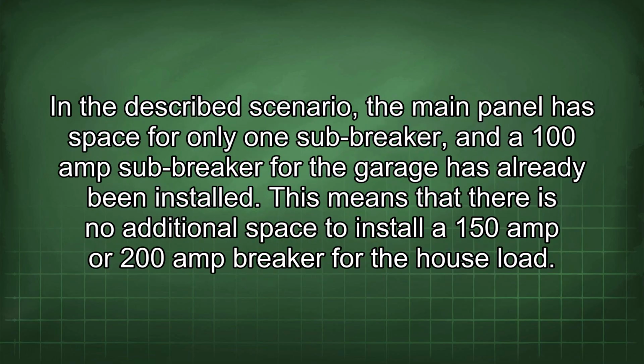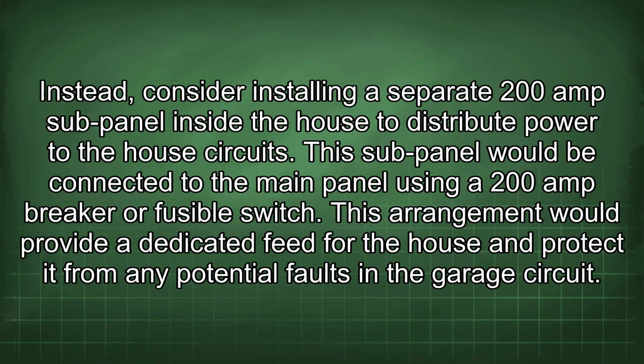In the described scenario, the main panel has space for only one sub-breaker, and a 100 amp sub-breaker for the garage has already been installed. This means that there is no additional space to install a 150 amp or 200 amp breaker for the house load. Instead, consider installing a separate 200 amp sub-panel inside the house to distribute power to the house circuits.